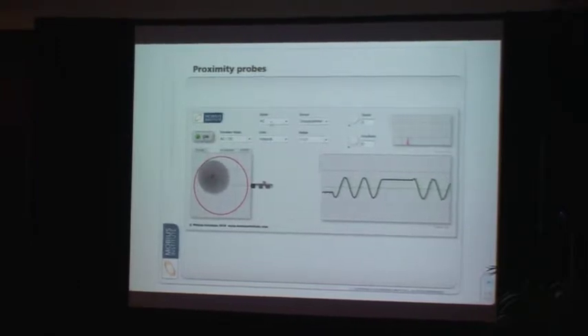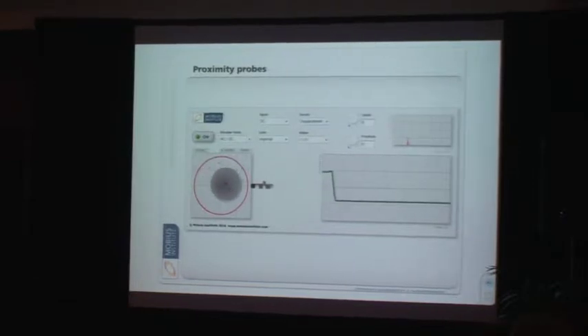The DC part is basically the gap between the center of rotation and the probe. Even though the shaft's moving, because of how the signal conditioning and processing works, we're really just looking at the average center position of the shaft relative to the probe. So it is sensitive to where this rotation is occurring, and that's important to us, because we want to know whether it's rotating around the center of the shaft, or off to the left, right, down, or over there. That's very important from a stability point of view, and to diagnose things like misalignment, because it's pushing the shaft over where it shouldn't be. So that's the AC part and the DC part.